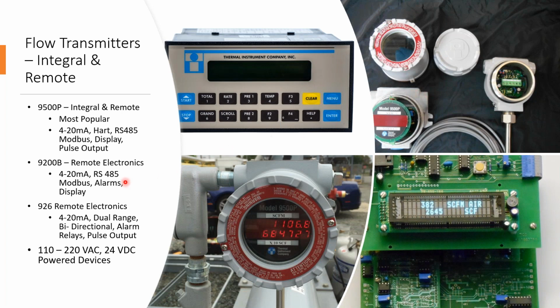Some of our other transmitters are the 9200B, which is this one up here. This is more of a panel mount. Typically we find these in control rooms where the sensors are out in the production area and then they're run back to this control room and used there. And then last but not least is our 926 remote electronics. This is kind of an older style of electronics, but it gives us the ability to not only deliver a flow output back to your control center, to your PLC, or whatever it's going to via the 4 to 20, but it can also do some bidirectional indication. So if you've got a condition where your flow might reverse and you need to know when it reverses, this unit can trip a relay to let you know, based on a sensor in the flow element going off, that your flow is reversed.